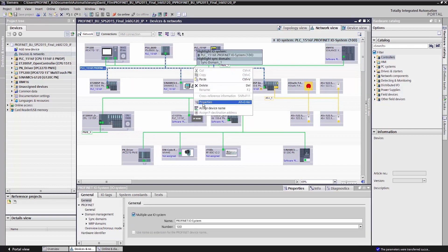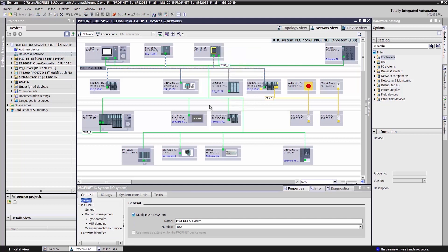I right-click on properties and check multiple use I.O. system. In doing this, I grant the TIA portal permission for the CPU to overwrite all IP addresses of the assigned I.O. devices.